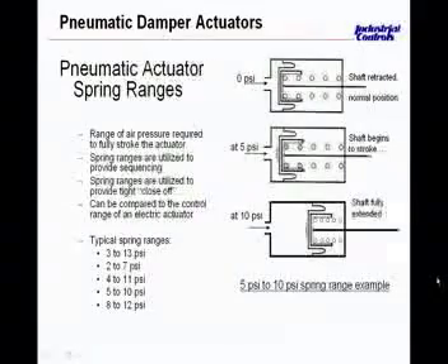If a positive positioner were installed on this actuator, the relationship of stem to branch pressure would be maintained, because we could admit up to a 20-pound branch to drive against the backside of that diaphragm so that we'd achieve the desired position. There's different spring ranges shown on the left-hand side, but most of your economizers, your cooling dampers will have the higher ranges, the 8 to 12, 8 to 13. 3 to 13s are shown here as well, but that's uncommon for a full range of control. Again, it depends on the application and what other components this actuator needs to sequence with as to what that spring range would be.